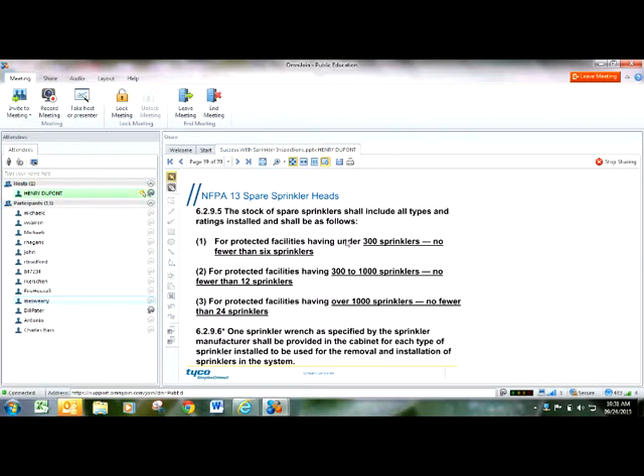If you've got a building with 300 or fewer sprinkler heads, you're required to have no fewer than 6 spare sprinkler heads. For buildings with 300 to 1,000 sprinkler heads, you must have no fewer than 12 spare sprinkler heads. And for buildings over 1,000, you have to have 24. You have to have a wrench that corresponds to each type of sprinkler head as well.